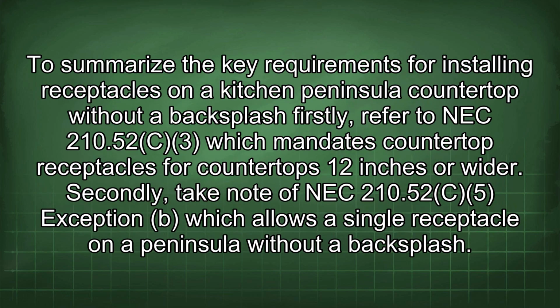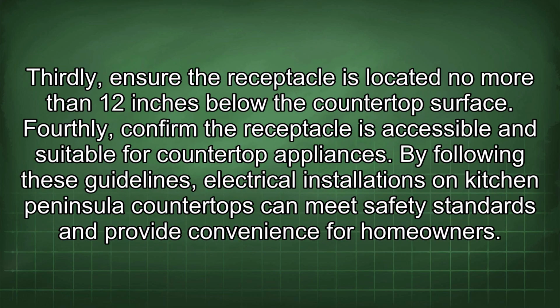To summarize the key requirements for installing receptacles on a kitchen peninsula countertop without the backsplash, firstly, refer to NEC 210.52C3, which mandates countertop receptacles for countertops 12 inches or wider. Secondly, take note of NEC 210.52C5 Exception B, which allows a single receptacle on a peninsula without a backsplash. Thirdly, ensure the receptacle is located no more than 12 inches below the countertop surface. Fourthly, confirm the receptacle is accessible and suitable for countertop appliances. By following these guidelines, electrical installations on kitchen peninsula countertops can meet safety standards and provide convenience for homeowners.